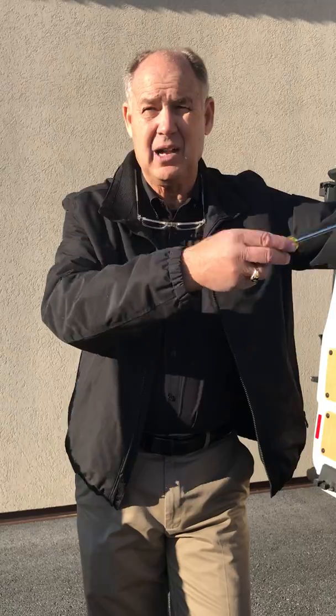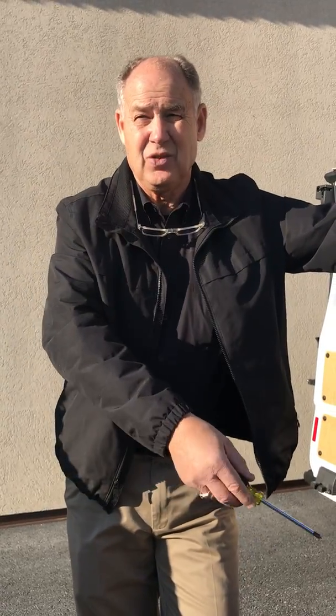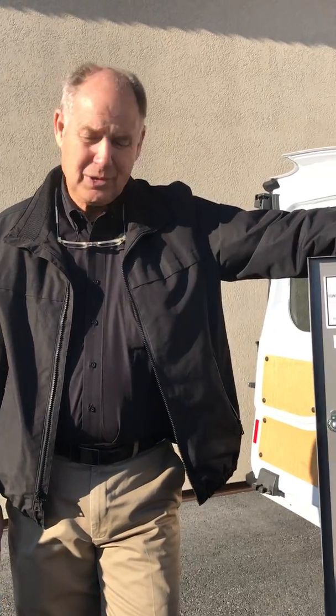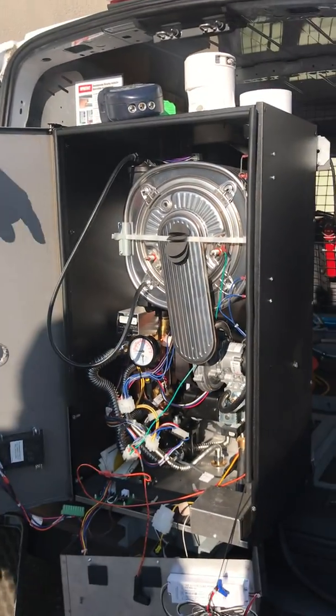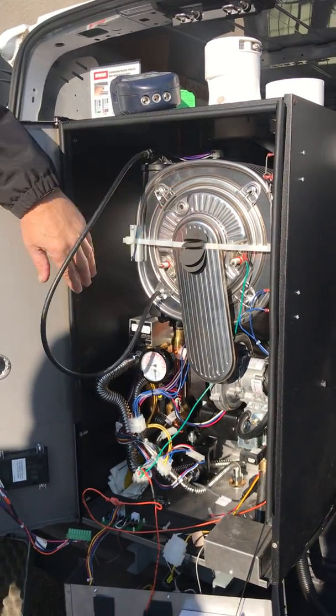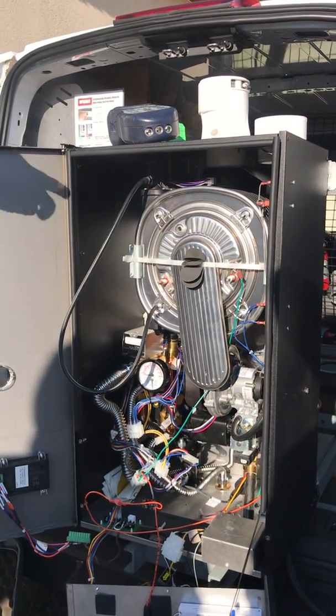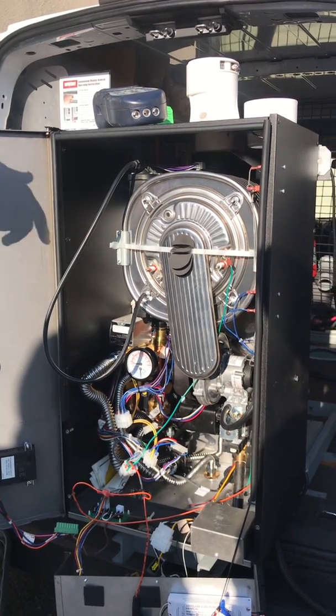Have you ever come across a cracked heat exchanger with one of these? Not on this style. I've had guys with other heat exchangers. This is taken down from the bottom. It's not coming from the top down in. So being that the pipe's down here, I don't get quite as much dirt and stuff in with these. No, I haven't had really issues with the heat exchanger. And what's really neat is you can buy just the heat exchanger. That heat exchanger is literally just bolted in here, and I've got to take my exhaust off. But the heat exchanger, you can pop out of there and change.